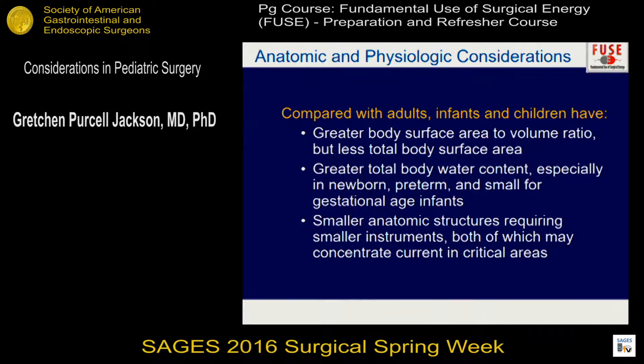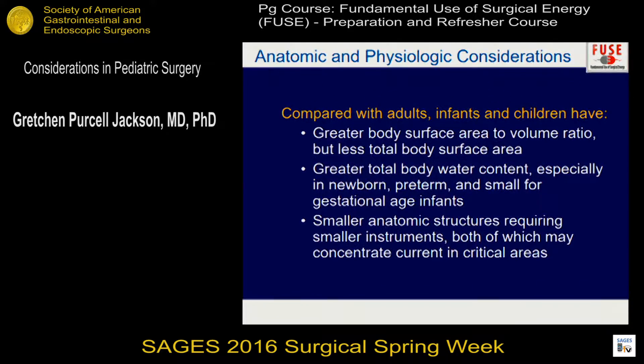Children have smaller anatomic structures, meaning we use smaller instruments. For those doing minimally invasive or head and neck surgery with tiny tips, that concentrates current — delivering more energy to anatomic structures. The structures are all very close together, so the risk for inadvertent injury goes up. And when someone is very small, any injury can be catastrophic.